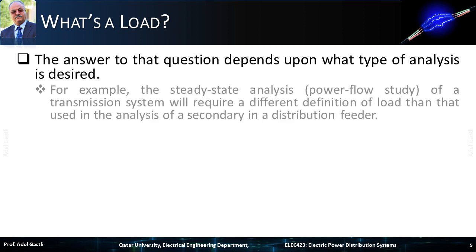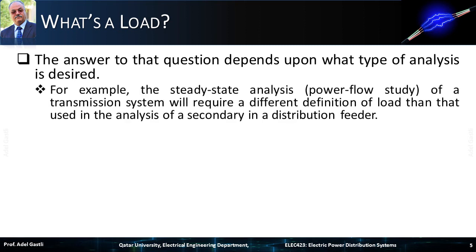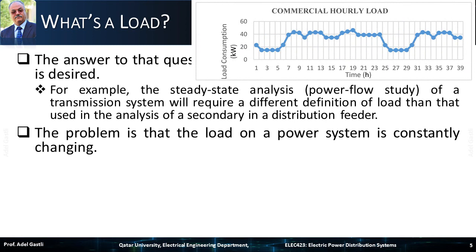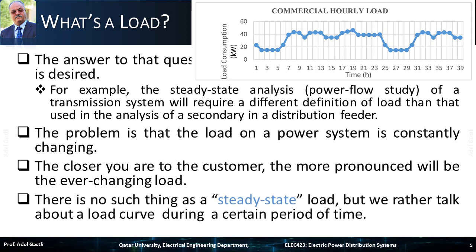What is a load? The answer depends upon what type of analysis is desired. For example, the steady-state analysis or power flow study of a transmission system will require a different definition of load than that used in the analysis of a secondary in a distribution feeder. The problem is that the load on a power system is constantly changing. The closer you are to the customer, the more pronounced will be the ever-changing load. So there is no such thing as a steady-state load; we rather talk about a load curve during a certain period of time.